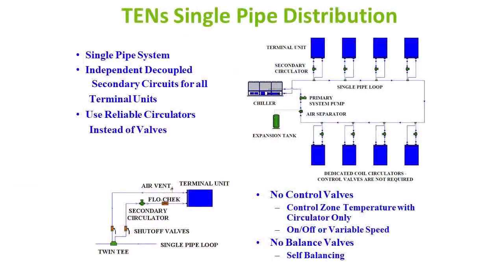All right, single pipe. Who's familiar with single pipe? A few of you. Okay, I'm not going to spend a whole bunch of time then. The biggest advantage to it is down here in the right-hand corner: there's no balancing valves. What it is, a single pipe, every terminal unit is a decoupled secondary piping circuit. So that means the flow in the primary does not affect the flow in the secondaries, and the flow in the secondaries does not affect the flow in the primary. Therefore, I can add and subtract those terminal units whenever I want, and I don't have to rebalance the main system. That make sense? That's the biggest advantage to the single pipe, and why it's being used in thermal energy networks.